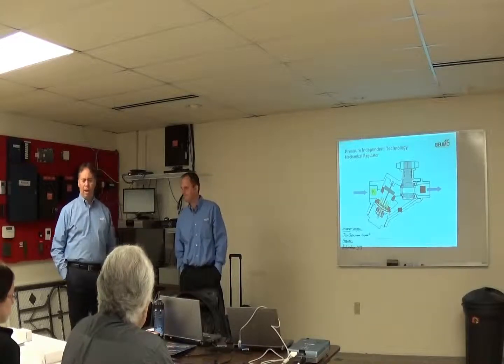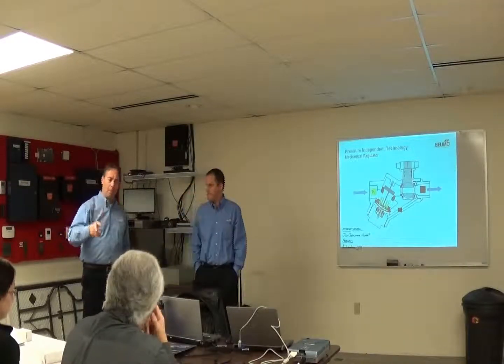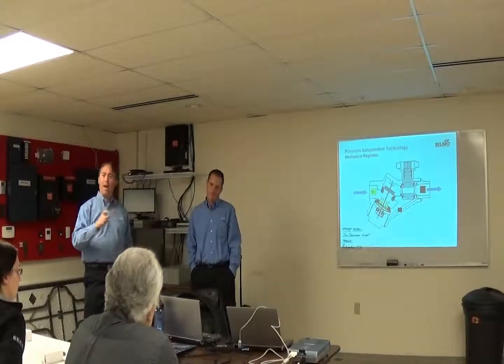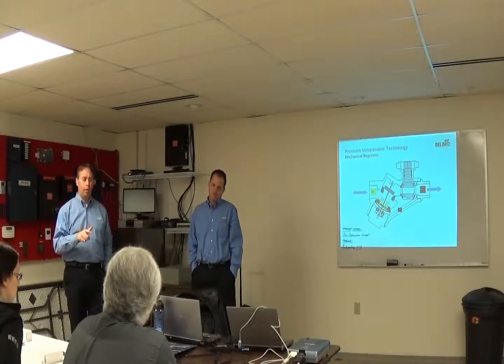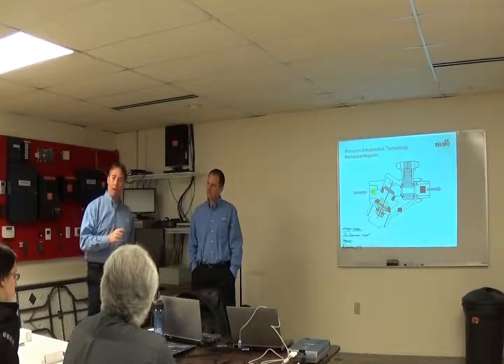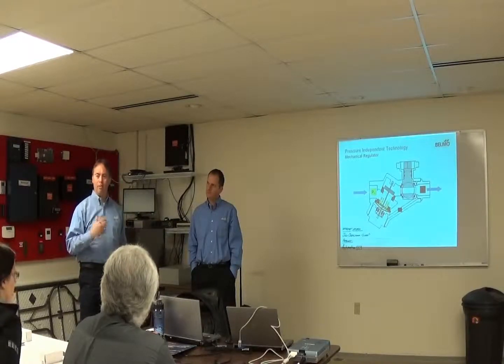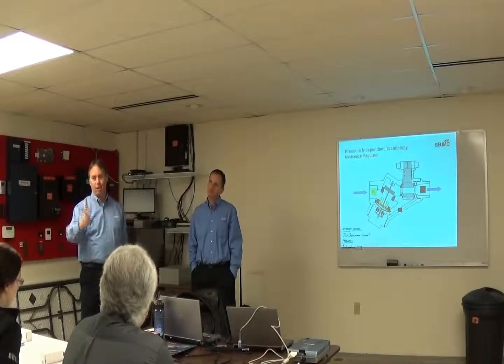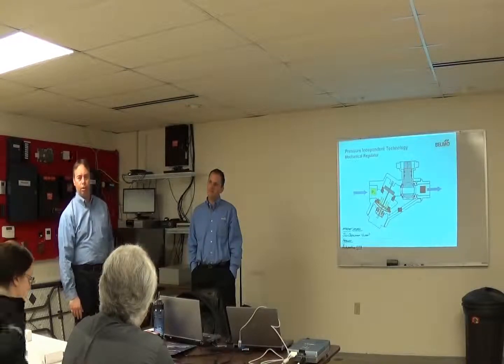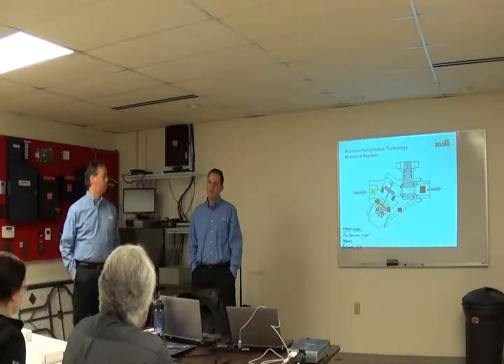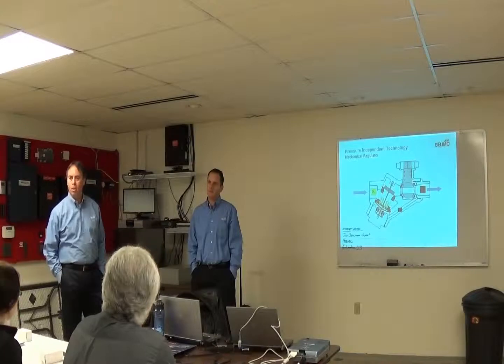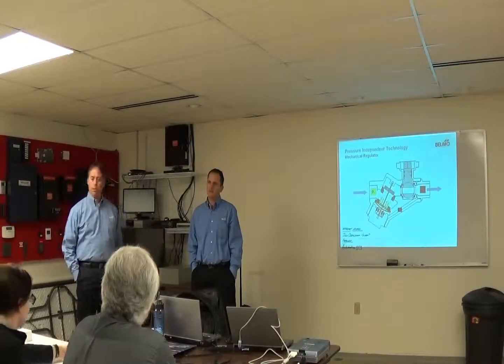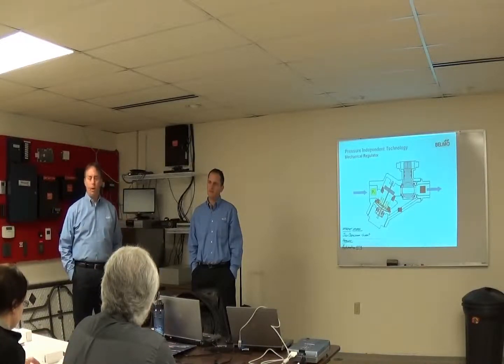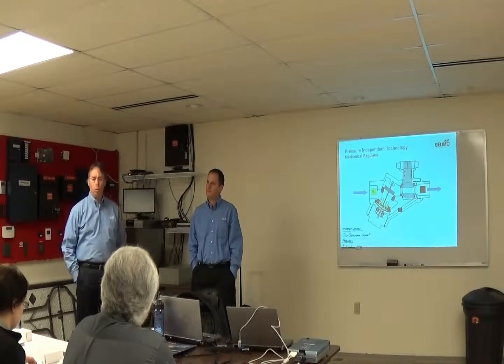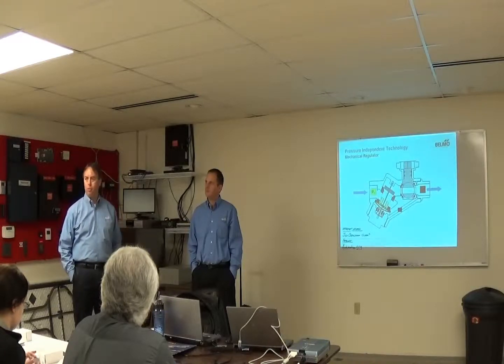Just FYI. And then one other thing I was going to mention, back to the pipe diameters ahead of the valve. The valve is still going to work if you have less than the 5 pipe diameters, it's just an accuracy degradation, exactly. The accuracy of the flow sensors, and these are about 2%. How about the longevity of that calibration and recalibrating it? Ultrasound, water treatment, all affecting it? No, no recalibrations required.